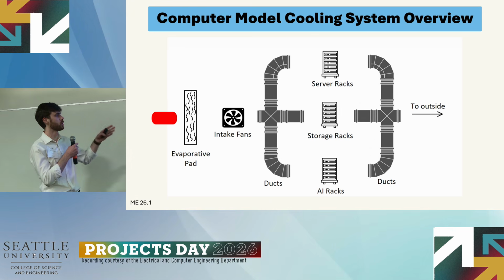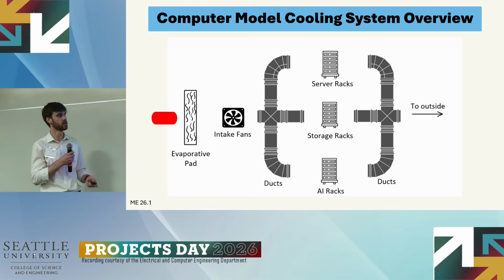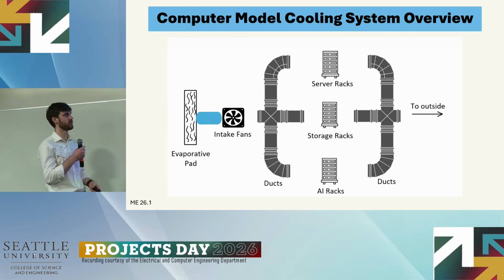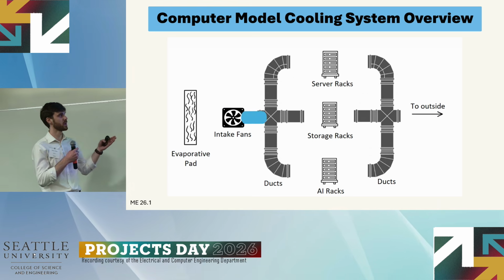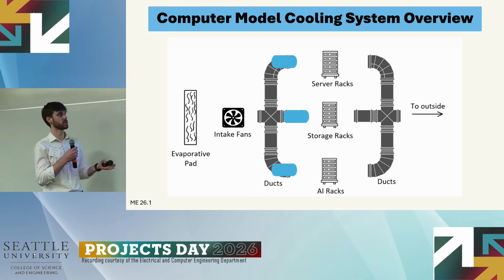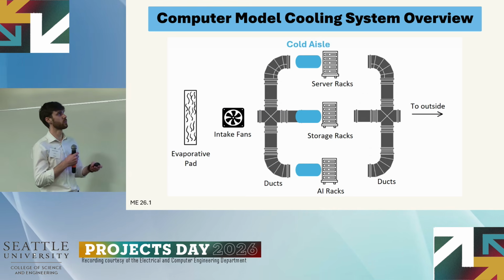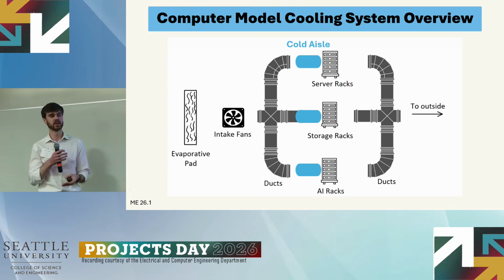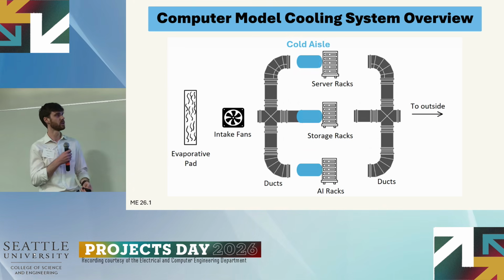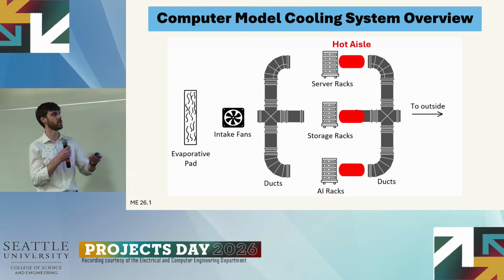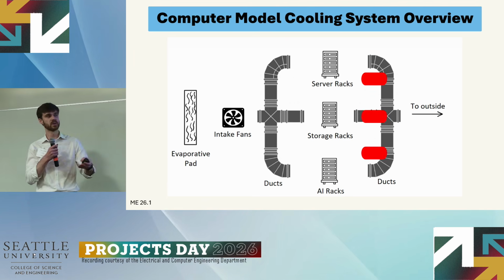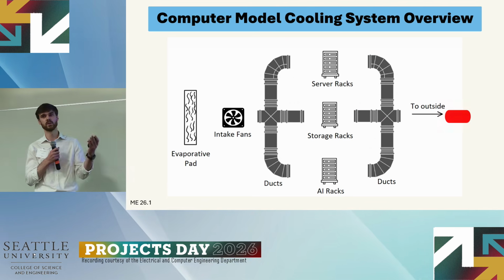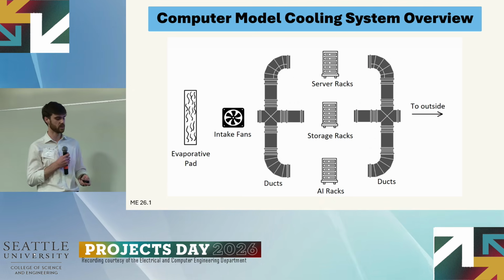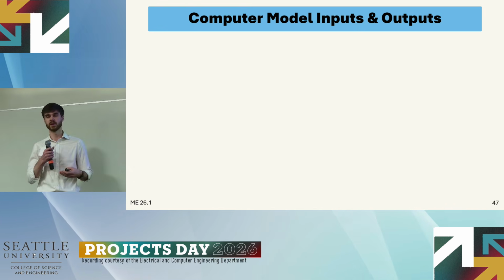We start with warm air outside of our data center. That air passes through the evaporative pad, cooling down. It then passes through fans, through the ducts, and into our cold aisle - the air before our racks. The air then passes through the racks into our hot aisle, taking the heat with it. This hot air is sent through more ducts, either to the outside or recirculated back through our data center. So what goes in and comes out of these models?